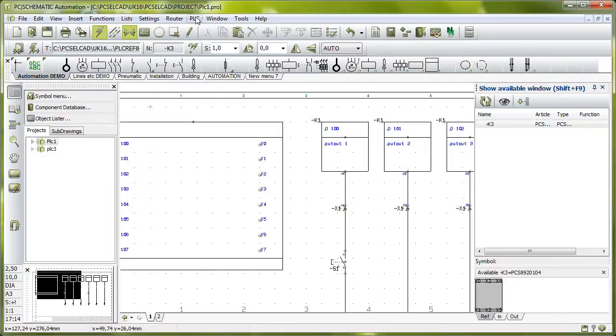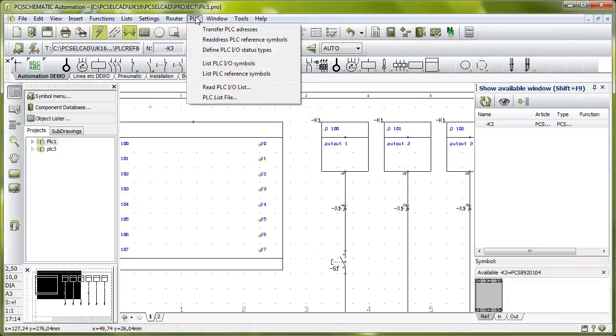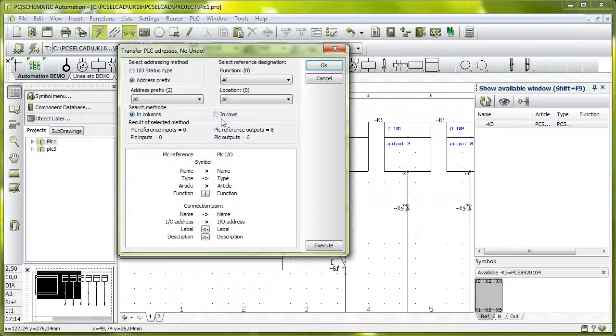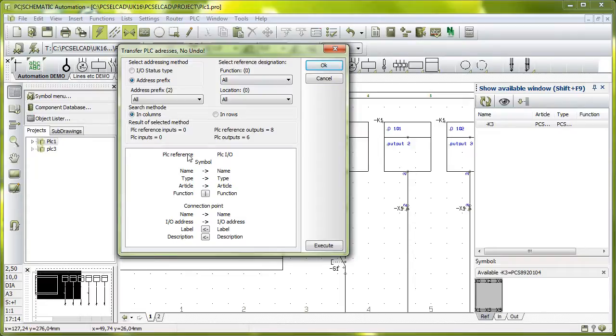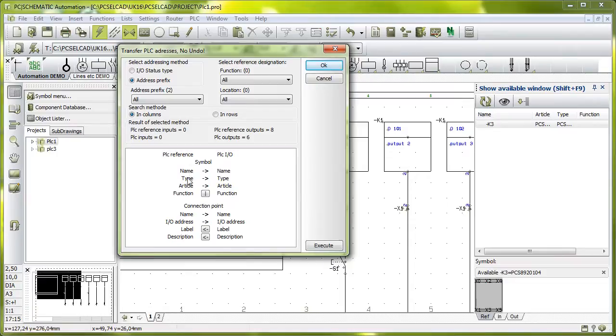I have in this menu here, the PLC menu, a menu item called Transfer PLC Addresses. Transfer PLC Addresses is a dialogue that makes it possible for you to transfer information from the PLC Reference Symbol. Remember, the reference symbol is the one that controls the name and the addresses. I can transfer a name, type, article number, connection point names, and my I.O. address.